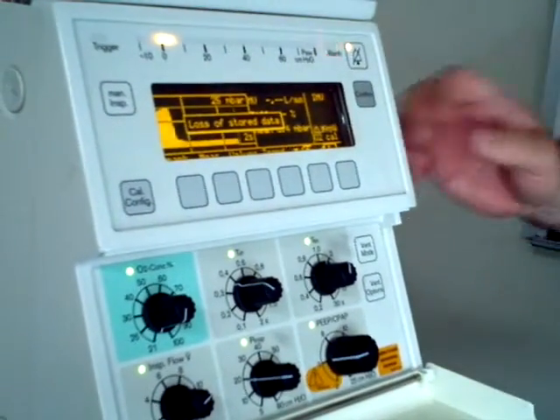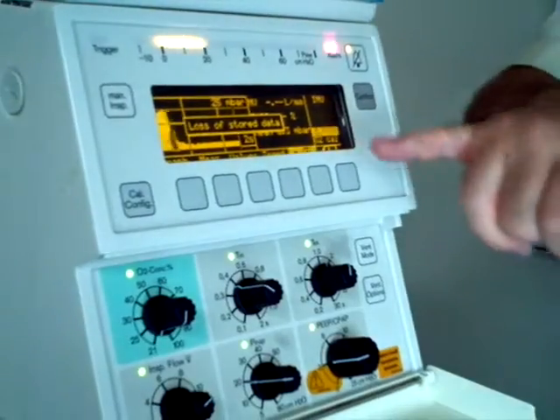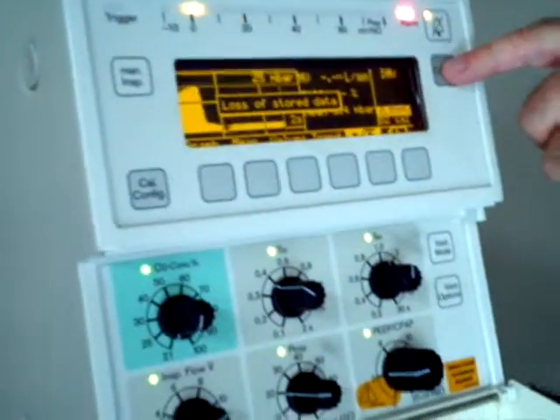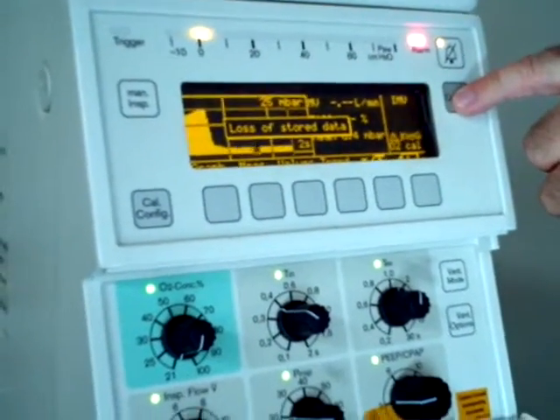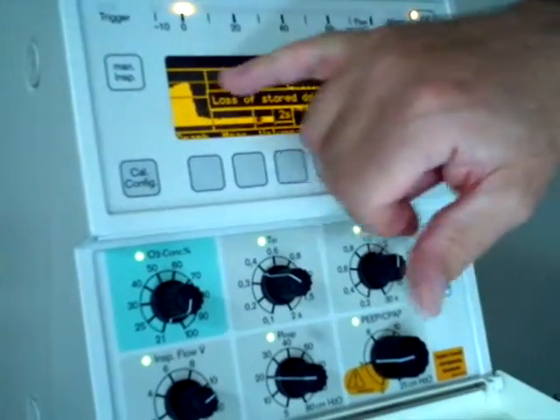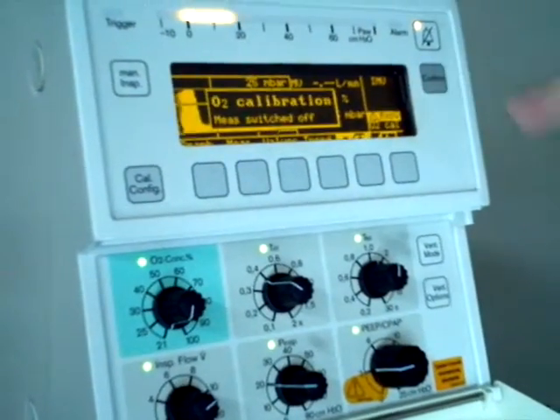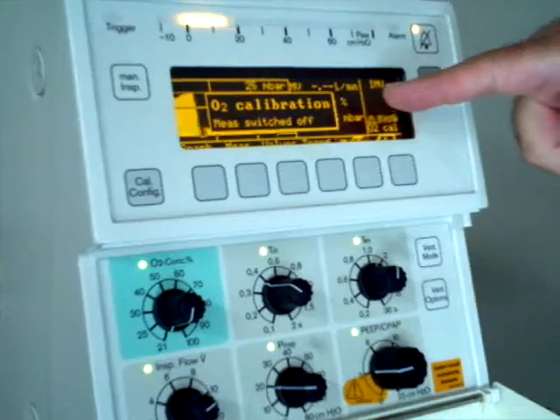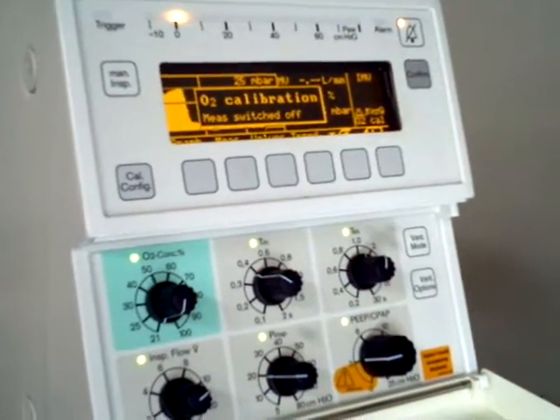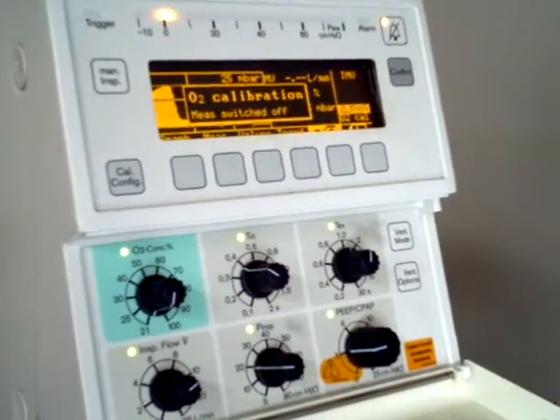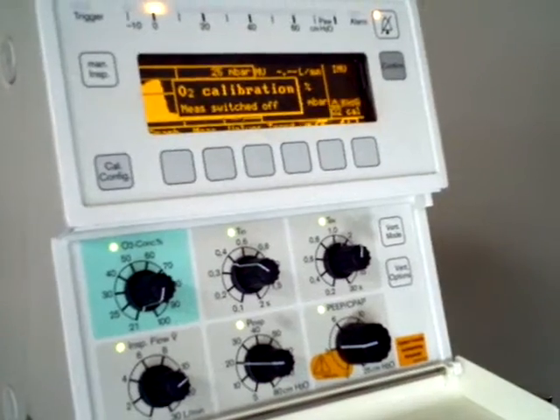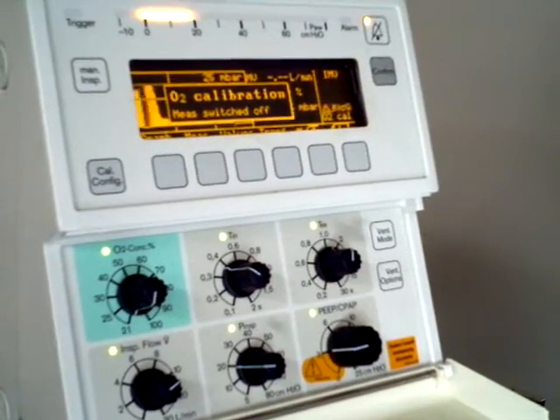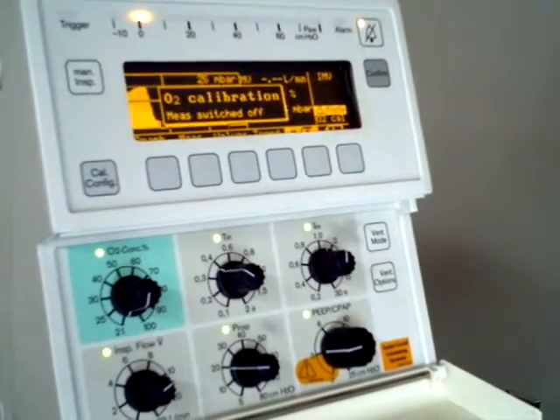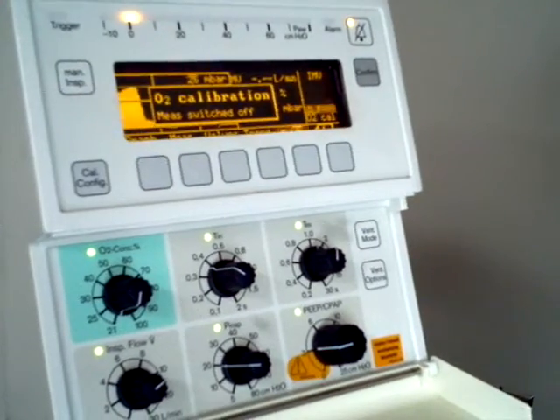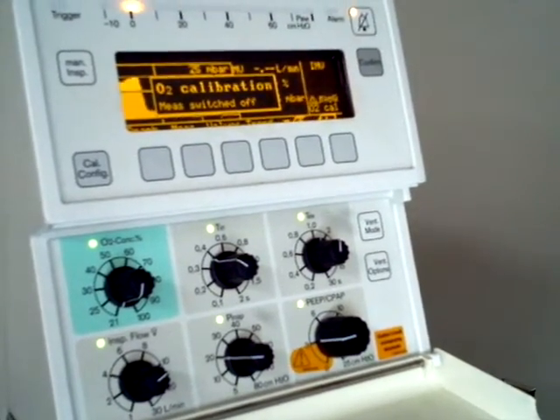Okay. As some of you found out, unlike the XL and the I that you were playing with, the confirm is just to get rid of or confirm the message it's trying to give you in the front. O2 calibration is done automatically. You can do an O2 cal, but really every time you do an O2 cal, it burns your sensor up a little bit quicker. So let the machine do it. We won't do one during the checkoff. I'll have you simulate one.